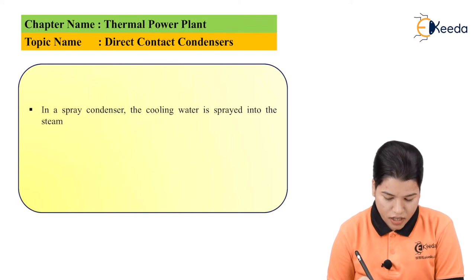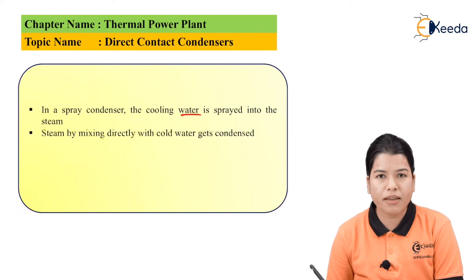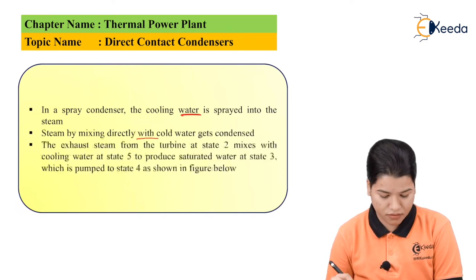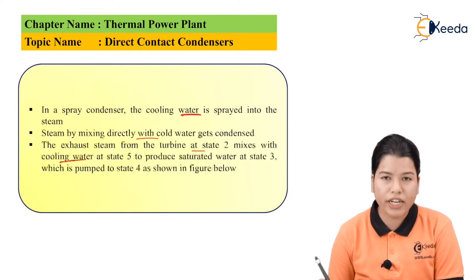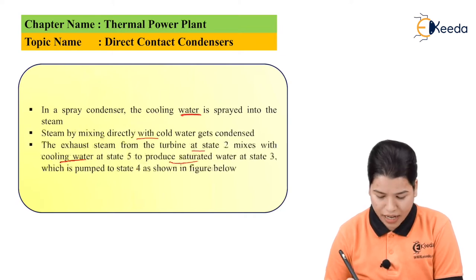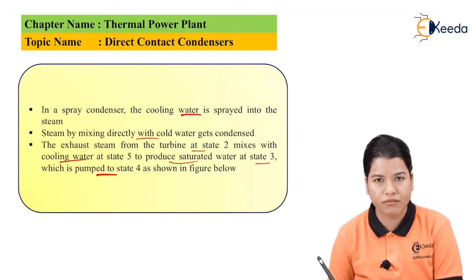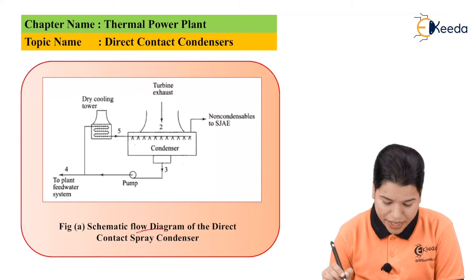In the case of a spray condenser, the cooling water is sprayed directly on the steam, so the steam mixes with the cold water and gets condensed. The exhaust steam from the turbine at state 2 mixes with the cooling water at state 5 to produce saturated water at state 3, which is then pumped to state 4, as shown in the figure below.